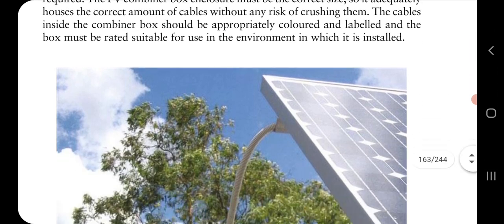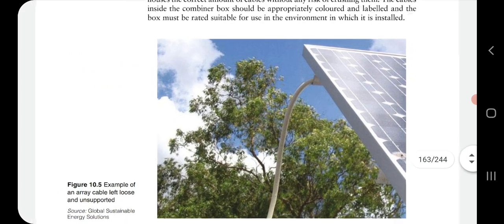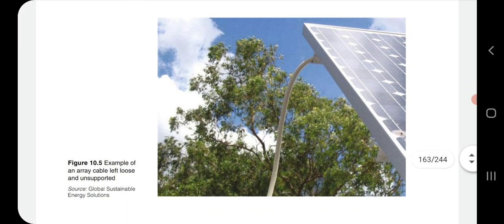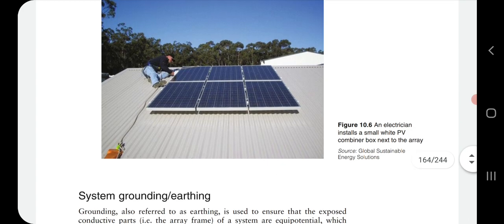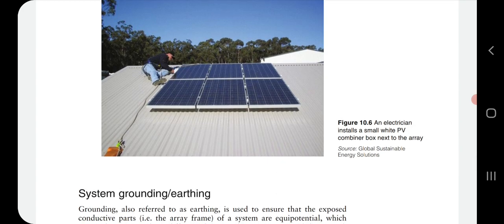If you see, this is an example, a loose example. This is a loose array cable. It doesn't have any support. It is left loose. And here, if you see, an electrician is working to install the PV array and is taking the cable or wire towards the PV combiner box.